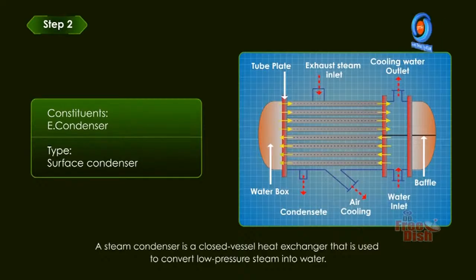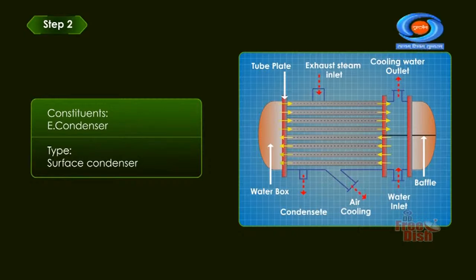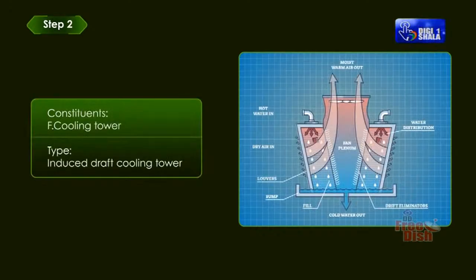A steam condenser is a closed vessel heat exchanger that is used to convert low pressure steam into water. It works to achieve two main objectives: to supply pure water to the hot well. Water from the hot well is again pumped into the boiler with the help of a boiler feed pump, and to maintain pressure below the atmospheric pressure at the outlet of the steam turbine so as to obtain the maximum possible energy. F. Cooling tower. Induced draft cooling tower.